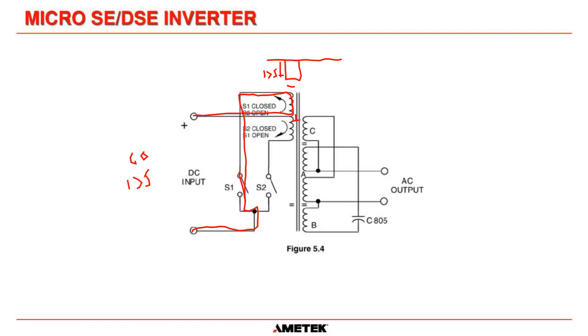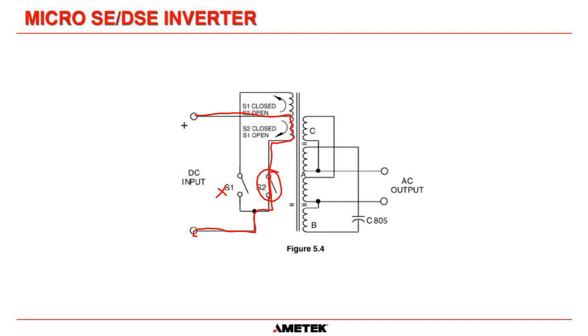So that's for the negative portion of the sine wave, with S1 closed and S2 open. Then all we do is open S1 and close S2. You can see the polarity of the battery itself doesn't change — the polarity gets changed through the center tap here. Now we go down this side of the transformer, down through S2, down to the negative. That makes this part of the transformer more positive than the other winding, which gives us a positive square wave. The previous one we did was negative, and now we've got a positive.